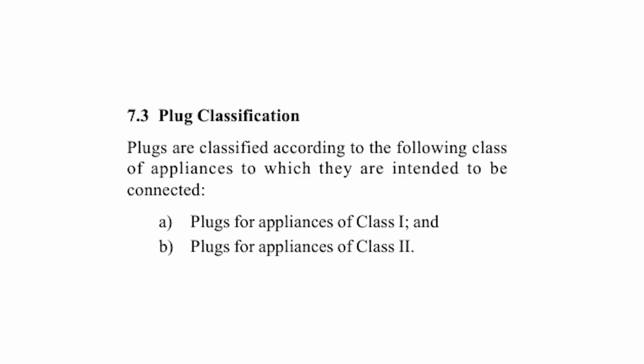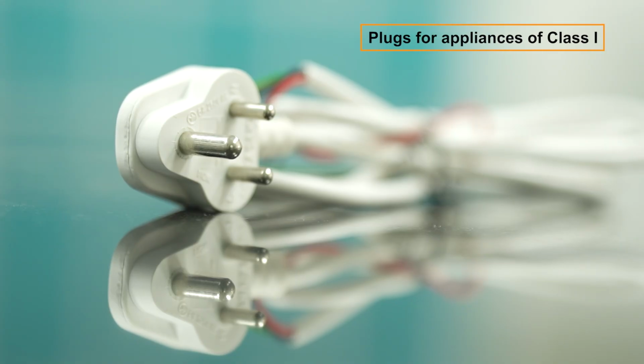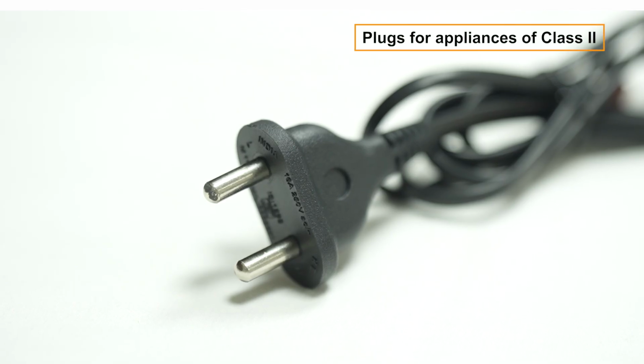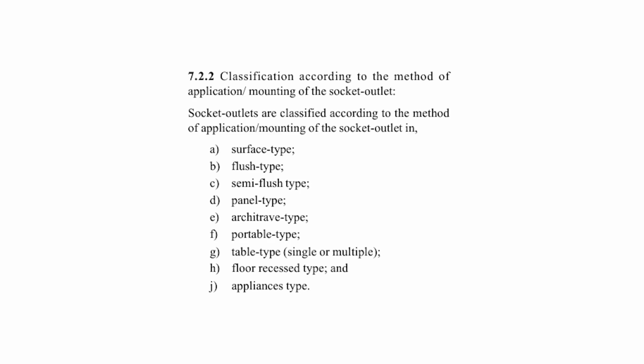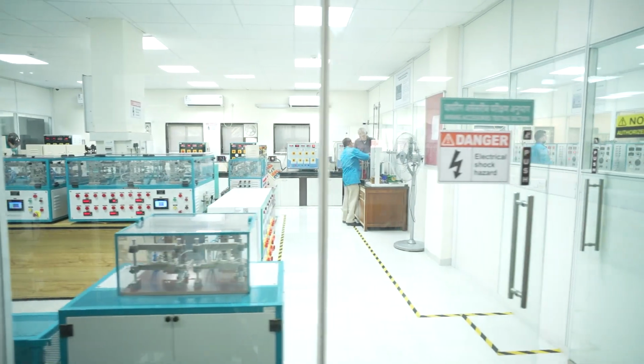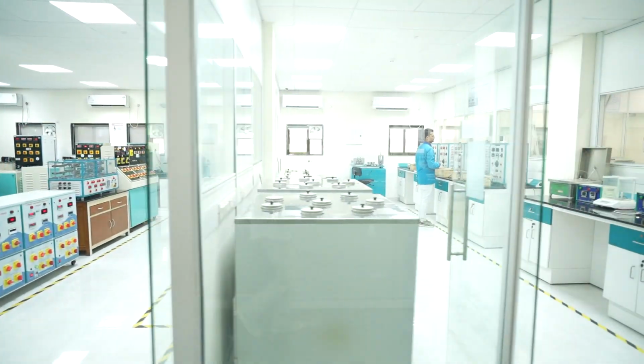Further, plugs are classified according to the class of appliances to which they are intended to be connected: plugs for appliances class 1 and plugs for appliances class 2. And socket outlets are classified according to the method of application or mounting on the socket outlet in surface type, flush type, semi-flush type, panel type, architrave type, portable type, table type, single or multiple, floor recess type and appliances type. Now, let's see how plugs and socket outlets are tested as per Indian standards.